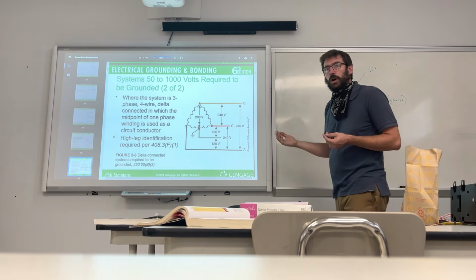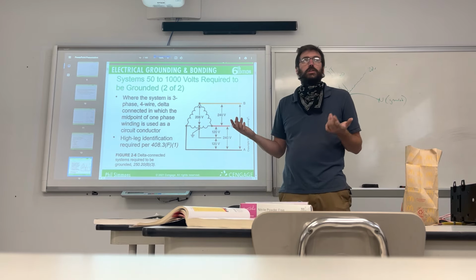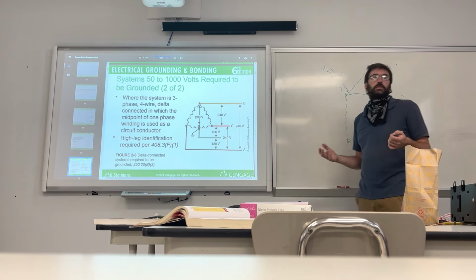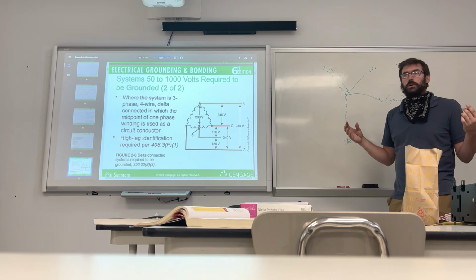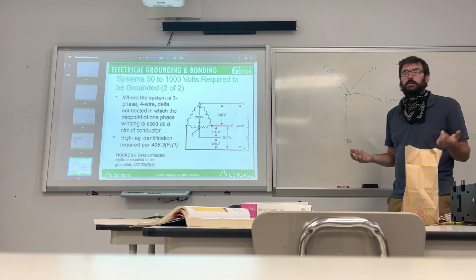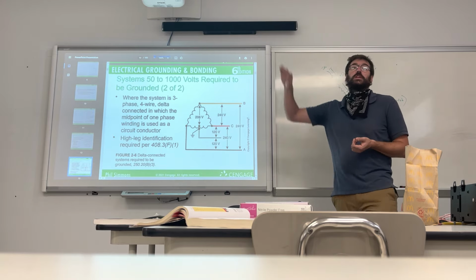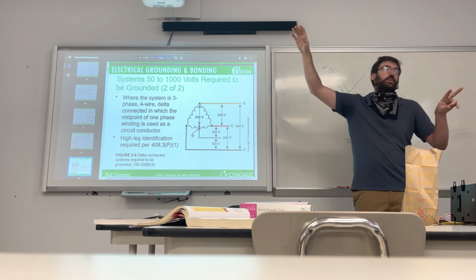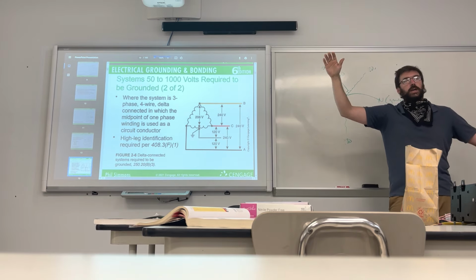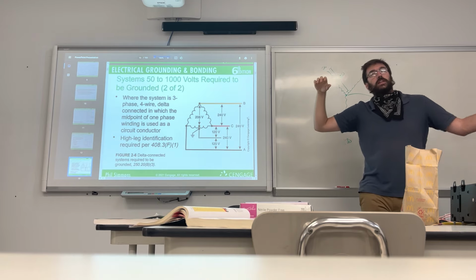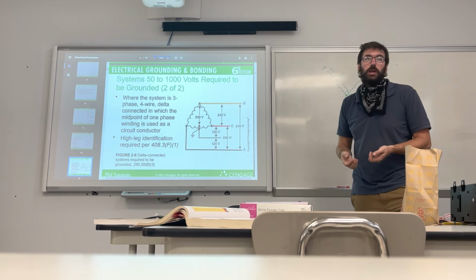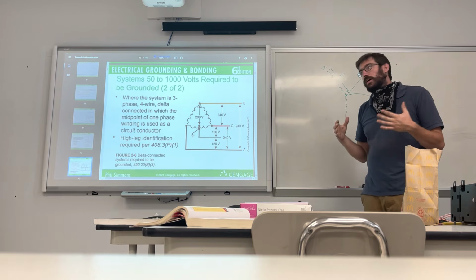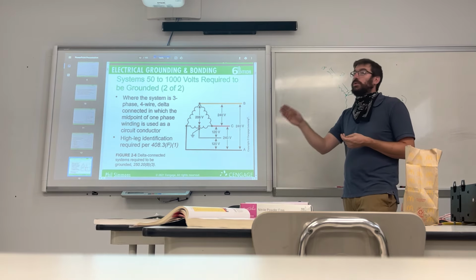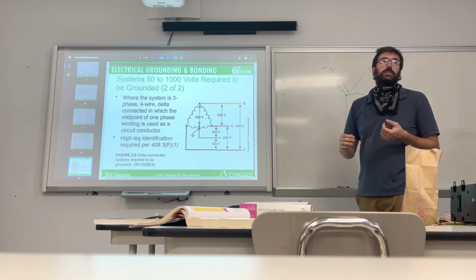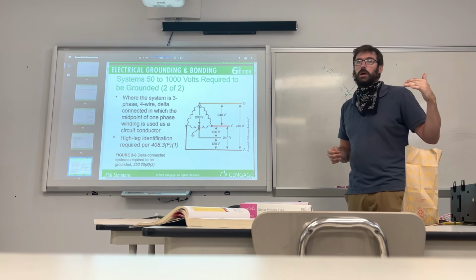The higher the volts, the lower the what? Amps, right? And you pay by the amp or you pay by the watt. So if you have a big commercial building, what's likely to be your biggest expense when it comes to power? Lights, right? So wouldn't it be nice if you can run your lights on 277 and you have two circuits available to run your outlets, which have to be 110. And you also have the option of making that two pole, so you can run things more efficiently if need be. So there are instances that wild legs are useful, but you really do have to label the panel box very well. You have to tell them what lines 1, 2, and 3 are.